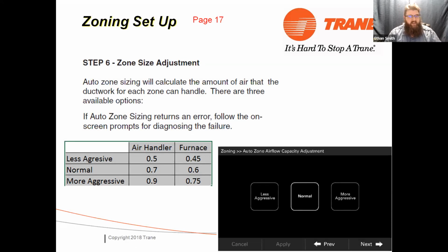So it does have a less aggressive, normal, and more aggressive setting. The less aggressive setting is going to optimize for a zone static of 0.45 in the duct maximum. Normal is going to set you for 0.6, and more aggressive is going to be 0.75 on those furnaces, and 0.5, 0.7, and 0.9 respectively on air handlers. Generally, I just recommend guys use the normal setting unless they're trying to address a noise complaint. Sometimes you'll get whistling registers or something like that, where you need to bump that airflow down a little bit, or they're not getting quite enough capacity, where you can bump that airflow up a little bit. So I'd probably start at normal anytime you do it and go from there.